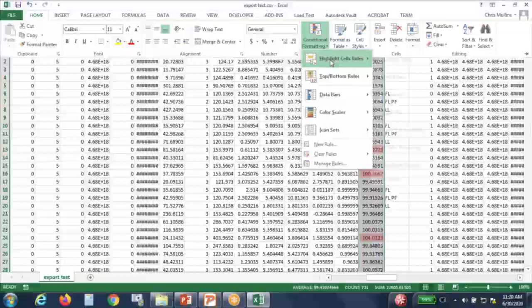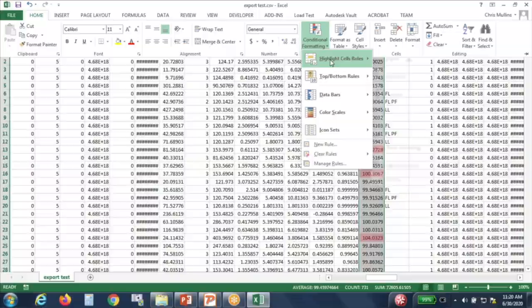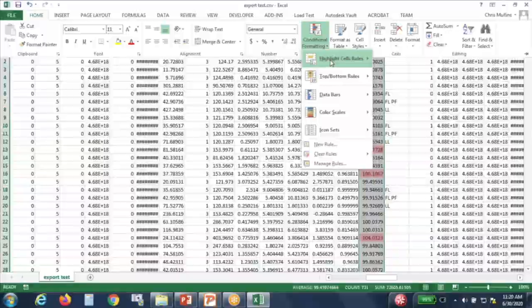But this one was a customer load test. That's a little bit below 0.85, slightly below here. A little bit off, but nothing too bad, right? Except for the ones that actually have a full load test. So that's another conditional format you've got. We looked at power factor, we looked at percent registration.